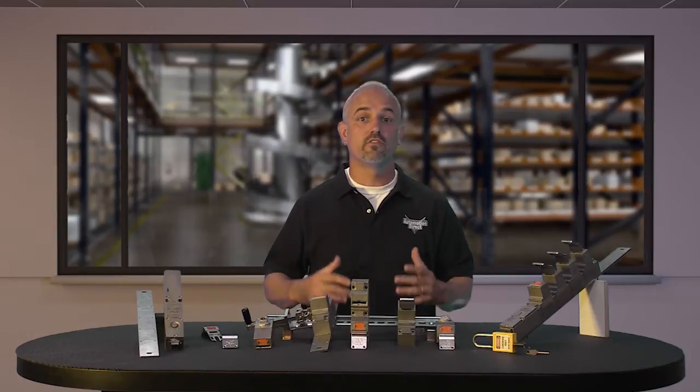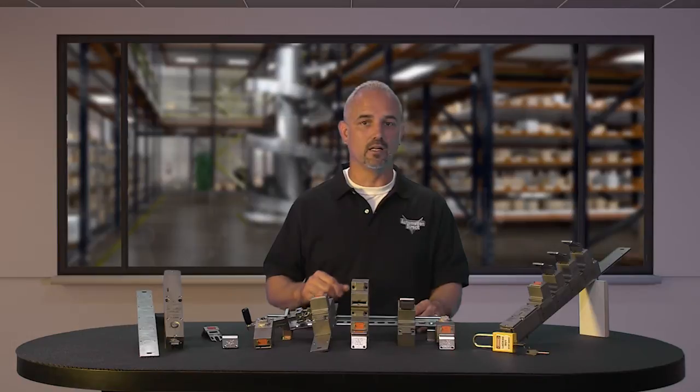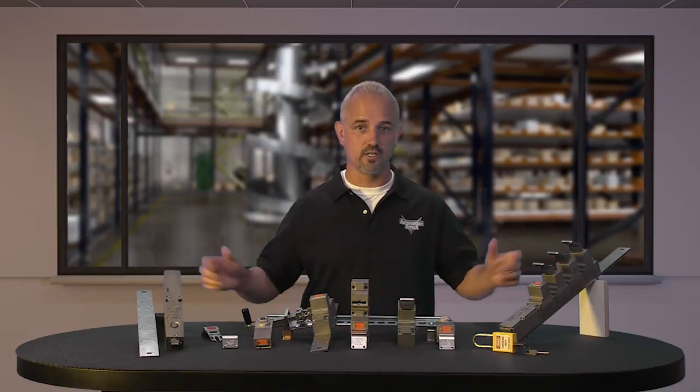This system allows the control of a series of lock points. Human operation of locking and unlocking provides first-hand observable safety. The trapped key system is cost effective for multiple locks over a large area and eliminates the cost of running electrical wiring over long distances.